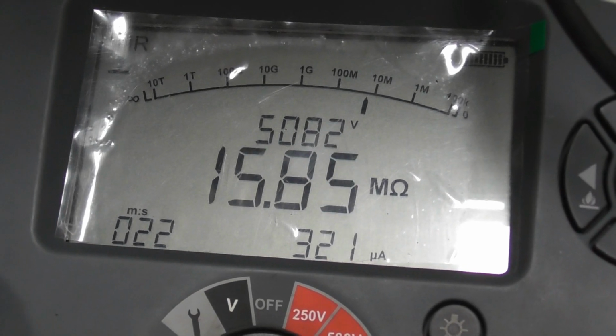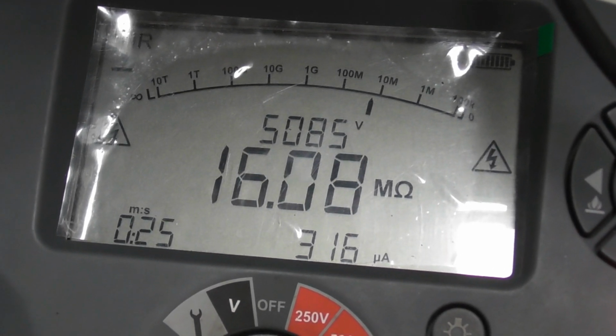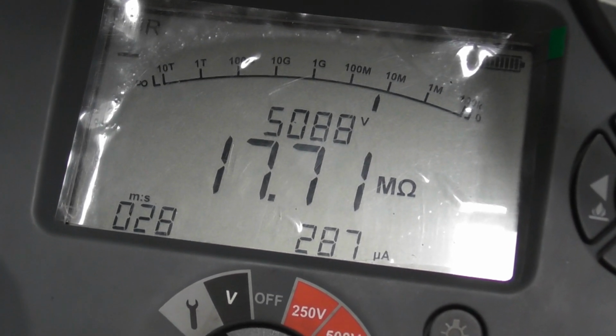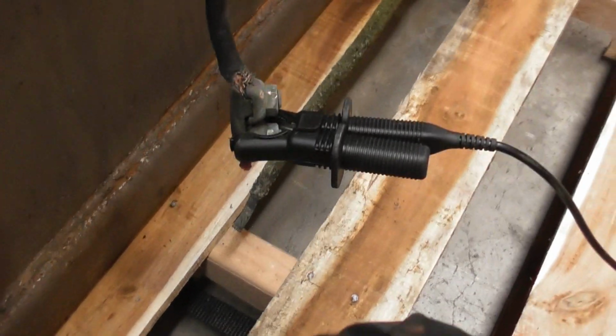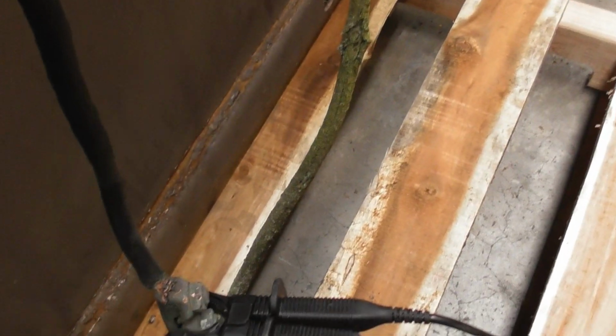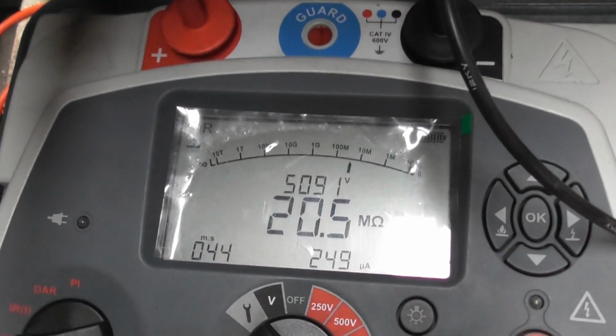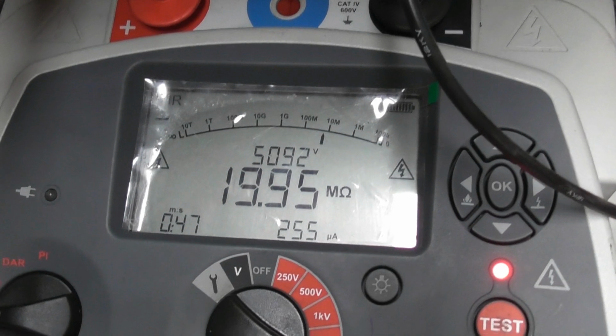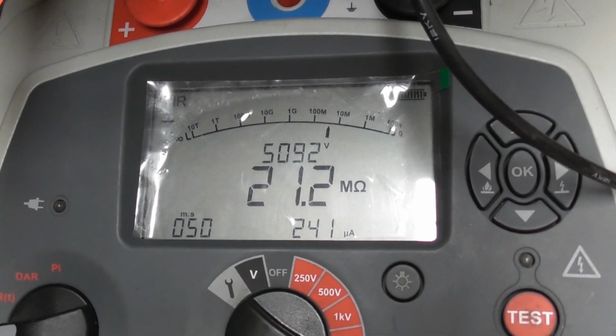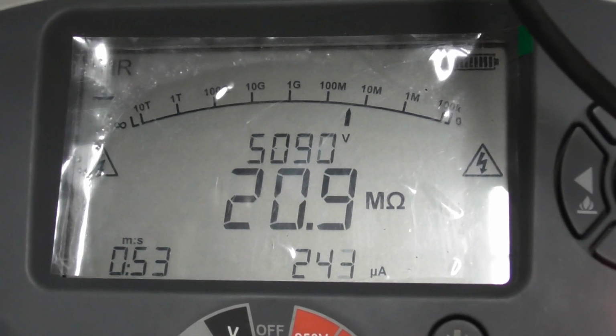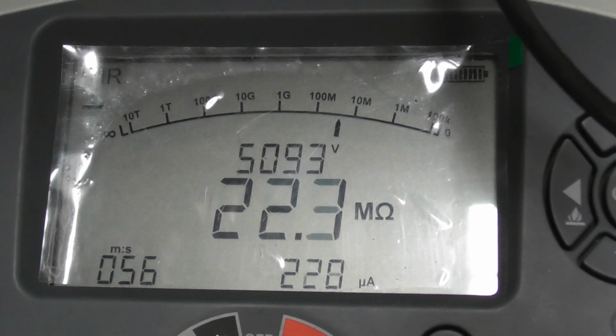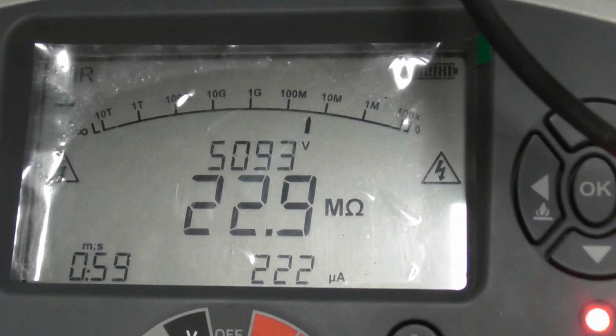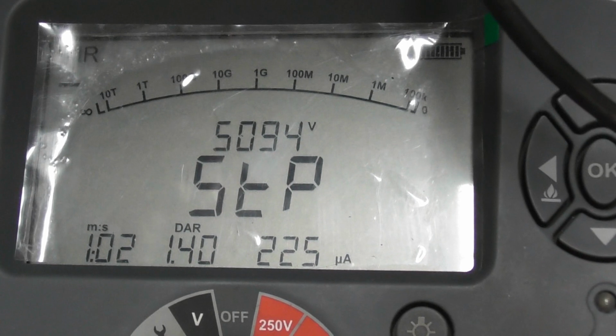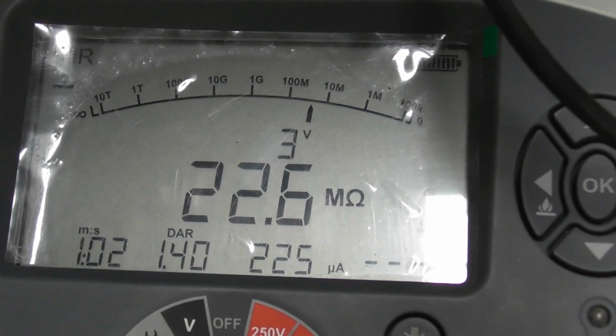But imagine this transformer is probably 60 years old. So primaries and delta, so it's important that the bushings haven't been cleaned. That wire connection and the other wire is floating, so it's not touching anything. I'll go for about a minute and then we're just making 20 megaohms. It's a bit low. I'll do secondary tests as well at 500 volts. So I'll make that up to about, say, 22.6 mega.